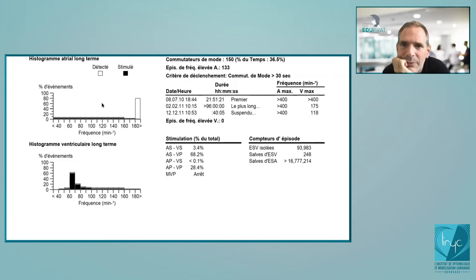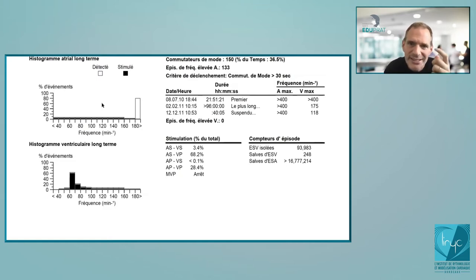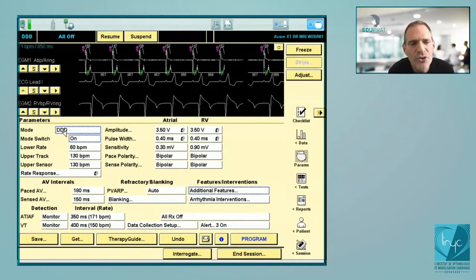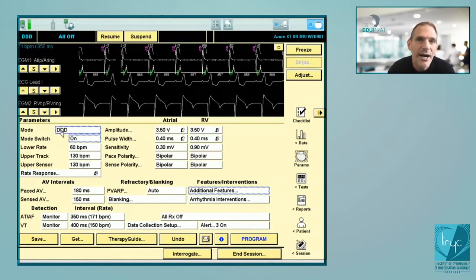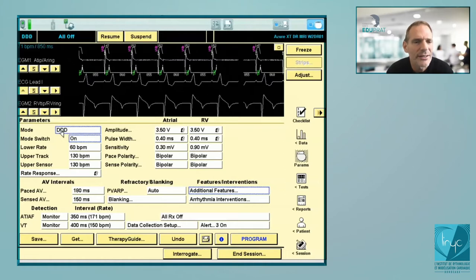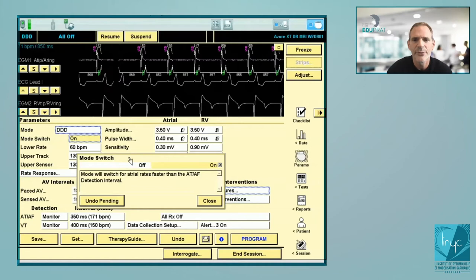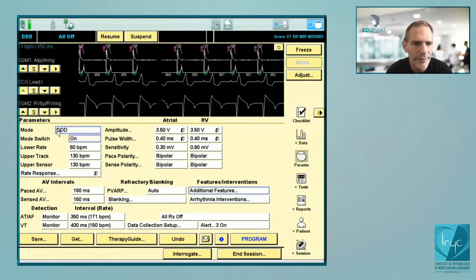In a patient with complete AV block in DDI without rate adaptive function, you would remain fixed at the minimal base rate. So you need this possibility. Nominally if programmed DDD, the mode switch — I will systematically recommend leaving it on. This is the capacity to switch from DDD to DDIR in case of atrial fibrillation. In Medtronic devices, dual chamber systematically means it will be DDIR.